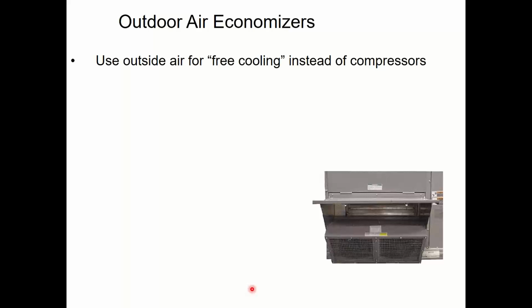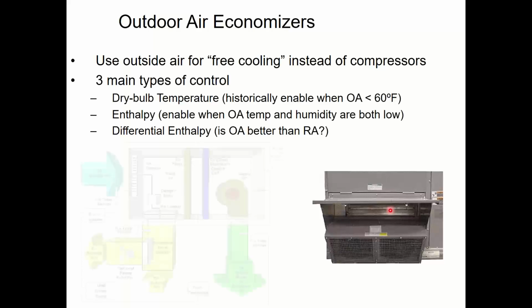So instead, what I'm going to do is open up a window in the mechanical equipment, in the rooftop unit, and use the fan in the rooftop unit to suck outside air in and use your duct system to deliver that cool outside air. If I want to cool the building and it's 57 degrees outside, don't turn the compressor on, just suck the cold air in. Boom, done. That's exactly what an economizer is. It doesn't have to be explained any more complicated than that. However, for your benefit, I'm going to explain it more complicated than that.